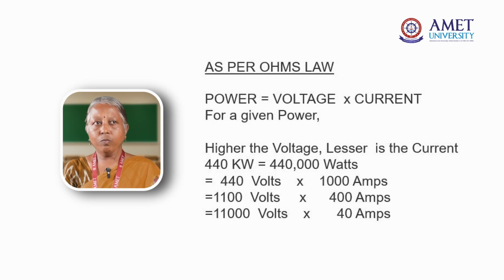When you increase the voltage, the current reduces. The equation of power is equal to the product of voltage and current. So for example, 440 into 1000 gives 440,000. But if you are taking an 11 kV generator, 11,000 volts into 40 amps, the power is the same, but the current is reduced and the voltage is increased.